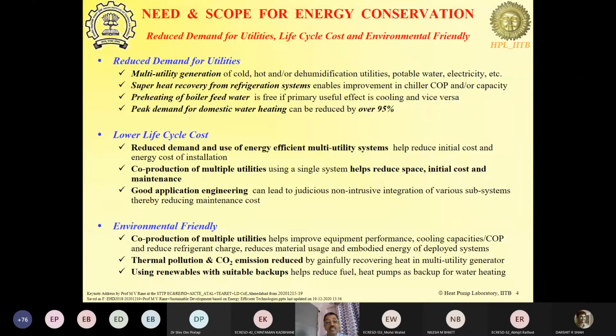Now, good application engineering is, however, necessary to ensure that the integration of the multi-utilities being generated using a single system still meets all the desired requirements of the user with respect to when they want the hot utility, when they want the cold utility, at what rate they want the hot utility or the cold utility is delivered, and so on and so forth. And of course, the primary objective of any designer should be to ensure that the reliability is maintained very high. Okay, so the user satisfaction is derived out of that. Now we'll look at environmental friendliness of these.